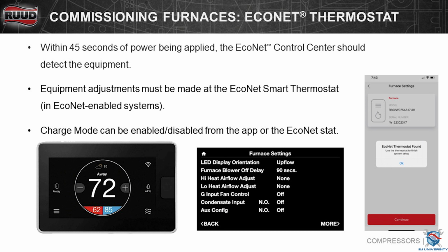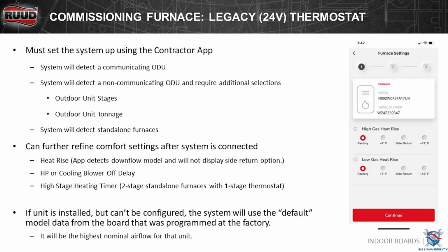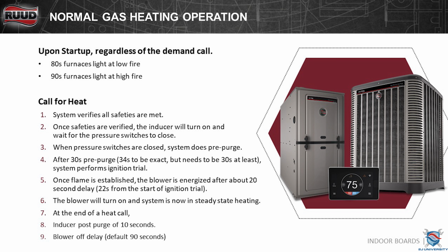Same with this, compatible both ways. You can either use the Contractor App, but if you have an Econet, you have to use the Econet on the furnaces. You can set stages, high heat, low heat. You can trim it however you desire. They've completely gotten rid of dip switches, and everything's done through the Contractor App now. So dip switches are completely gone on your variable speed boards. Everything's a toggle within the Contractor App.